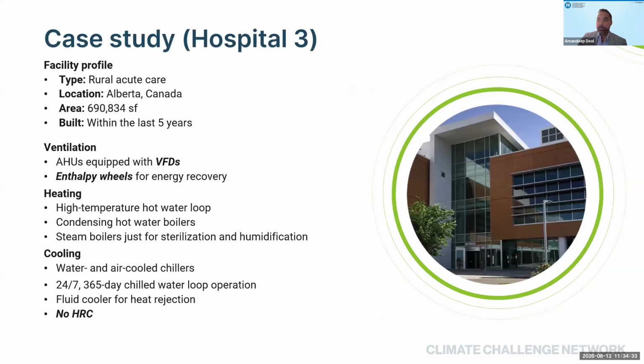Hospital 3 is a large rural acute care hospital, almost 700,000 square feet, and was built similarly in the last 5 years. It had all the features of the other hospitals, like VFDs, enthalpy wheels, and condensing boilers. However, one thing that's different is that, because of the design requirements, this hospital did not have a heat recovery chiller. That becomes a fundamental difference in the design from a high performance hospital. In that scenario, all your 24/7 load, which is reclaimed from your 24/7 systems like MRI and CT scanners, gets ejected outside to the atmosphere, versus using a heat recovery chiller to reclaim that and put it back into the building, eventually lowering your gas consumption.